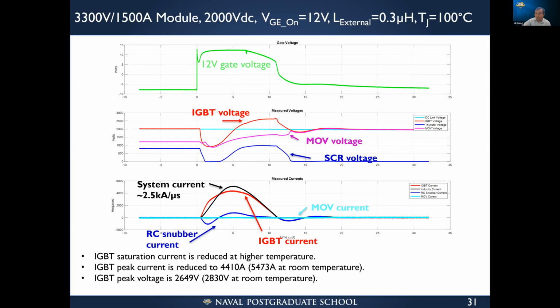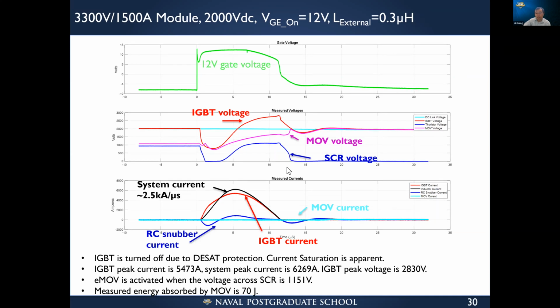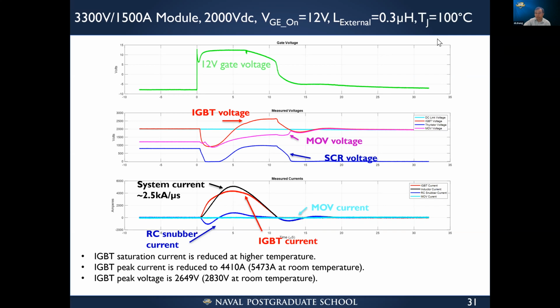But as expected, the higher the temperature, the higher the VCE, and the lower the saturation current level, which is all good to help improve the performance of solid-state circuit breakers. In these examples, this is room temperature, and this is 100 degrees junction temperature. So peak current is reduced from 5,500 amps to about 4,400 amps because the junction temperature increased. This will be closer to a real case when the device is carrying load current. And because of the lower current, the peak voltage is also reduced to about 2,650 volts from 2,830 volts.